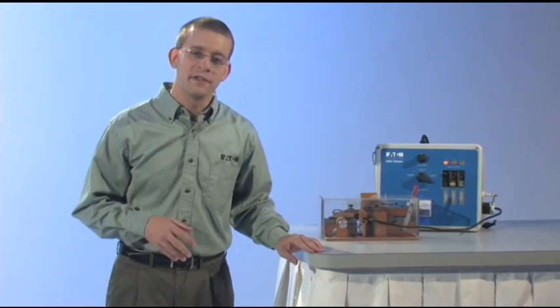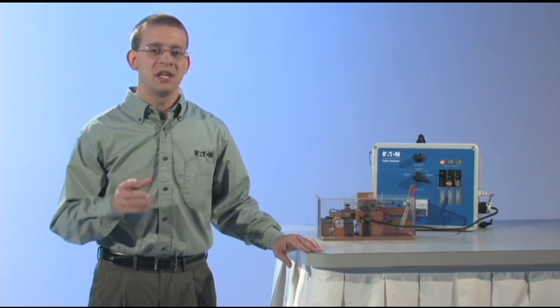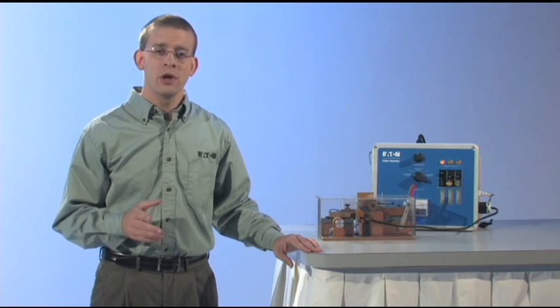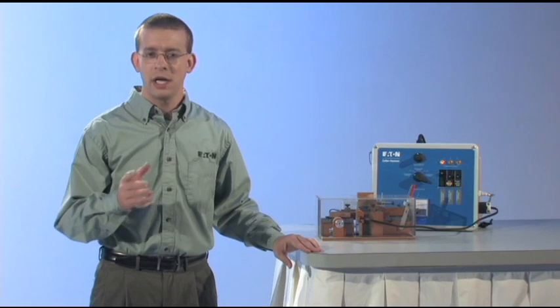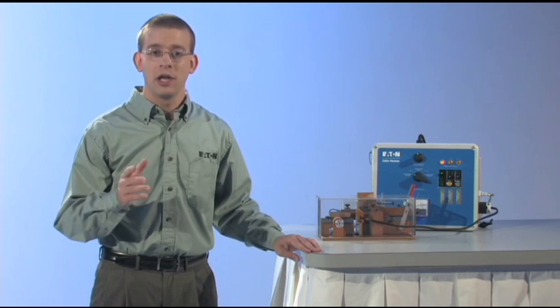The next type of breaker that was developed for residential applications was the arc fault circuit interrupter, or AFCI. Studies done during the early 1990s showed that a significant amount of residential electrical fires were being caused by a phenomenon called high current arcing. These situations occur when the insulation on the current carrying conductor is compromised and the current is given an arcing path.